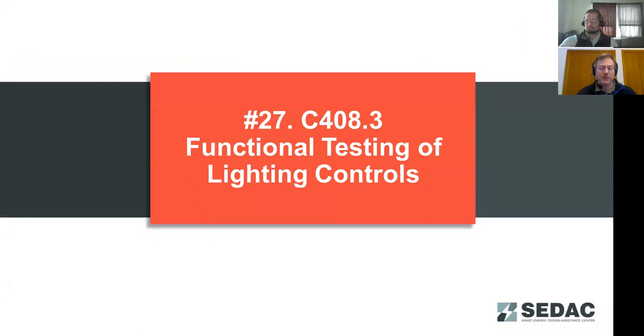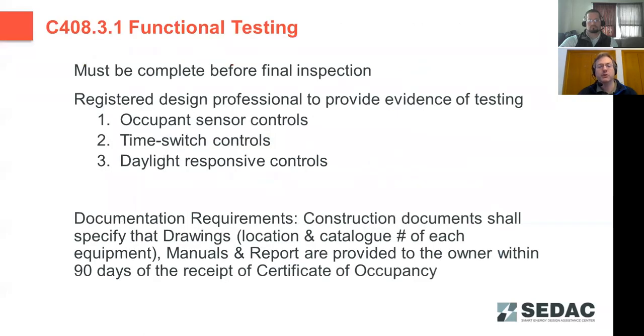So as far as functional performance testing, here we're getting into commissioning. The code calls out that we have to commission 3 different types of lighting controls. First being occupant sensor controls, second being time switch, and third being daylight responsive controls. So with this, the more controls we add, the more complexity we have, and the more chance of things failing. So with the documentation of this, notes similar to the HVAC controls, that the construction documents need to include specifications for commissioning. And it also notes that the manuals and the report need to be provided to the owner within 90 days of the certificate of occupancy.